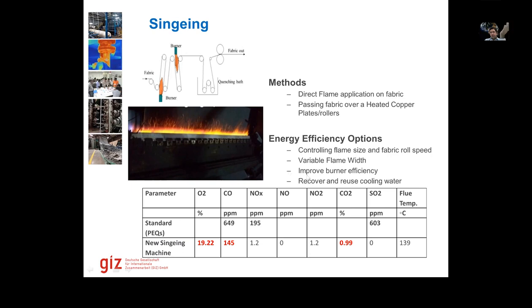Burner efficiency is something nobody generally looks at, but if we do a stack analysis, for example, look at the bottom - there was a machine for which we did a stack analysis, and the oxygen quantity was very high. If oxygen is too high, it carries too high a flue gas temperature as well, and because the air supply is very quick, we need to control it.